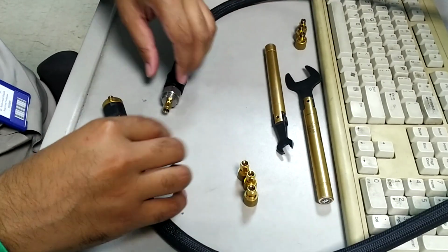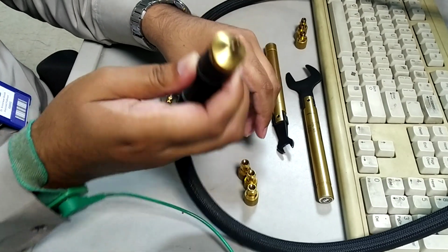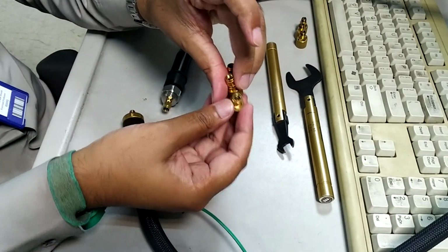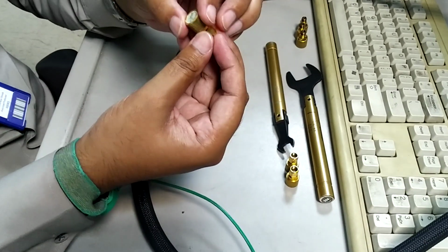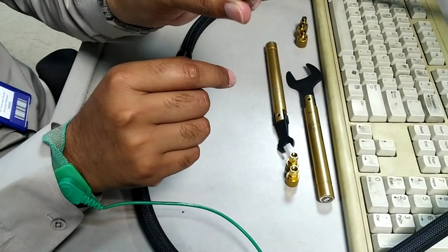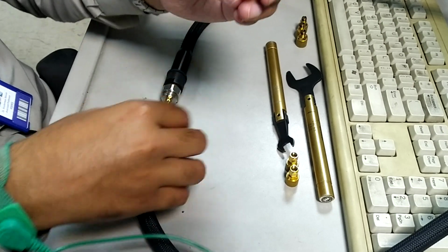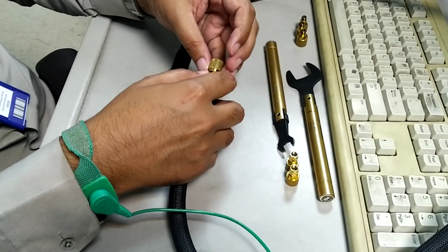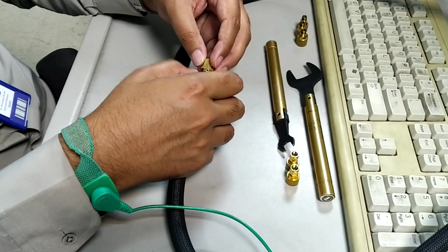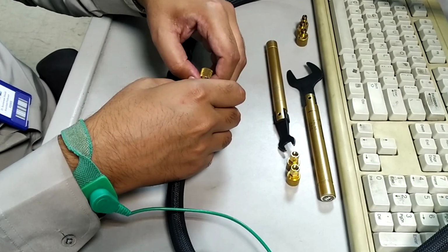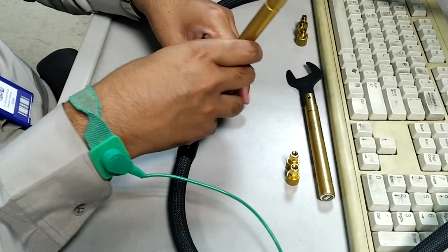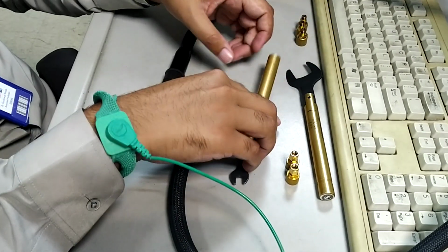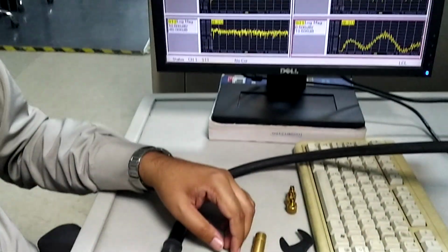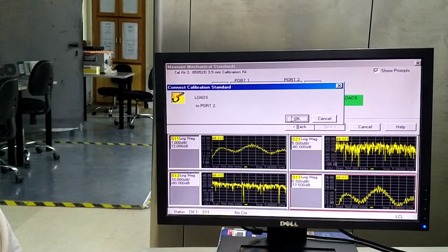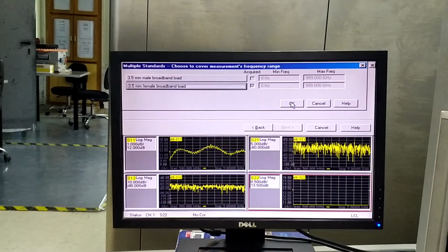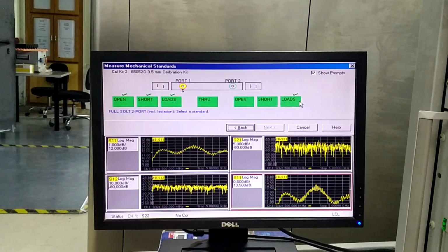Calibration standards have been connected. Now I use port number 2. Since this is a female port, as you can see here, the available calibration standards are all male calibration standards, so I can start with any one in front of me. The one available in front of me is a broadband load standard. You can see here, this is a male standard, so I connect it right here, and then I do the torque just to ensure that it's connected. So I connect a load standard. I click here, load. It's load to port 2. It's 3.5 mm female broadband load, okay. So the green sign has appeared. So load measurements have been saved.